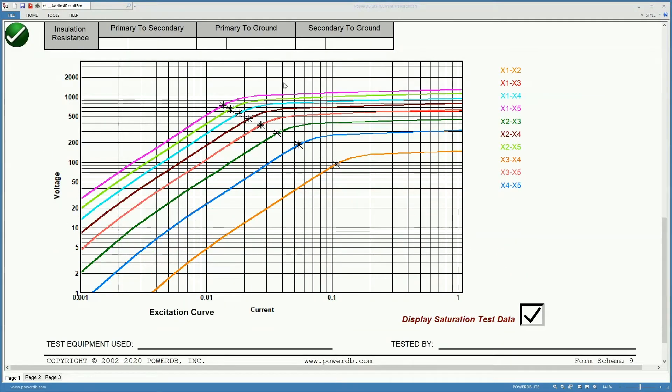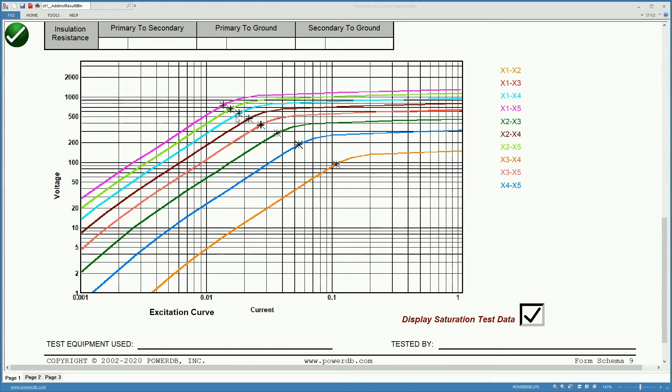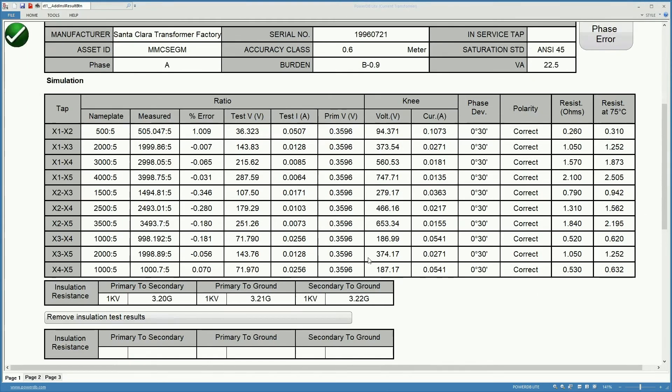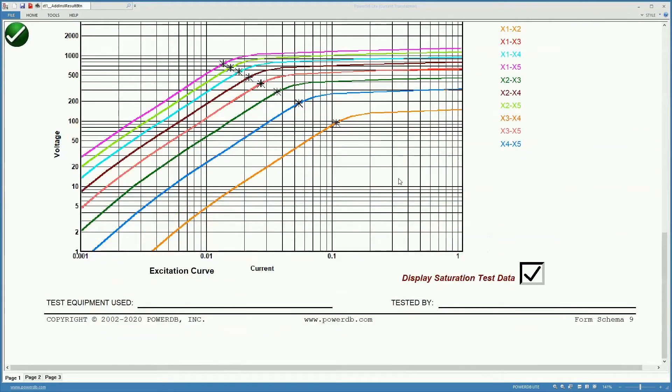If we scroll a little bit down, we get the excitation curves for the different taps. They are color coded. So for instance the X1, X5 is pink and it is the one on top over here. The values for the different knee points shown in this logarithmic graph coincide with the knee points calculated and shown on the previous graph. We can choose whether we want to display the saturation test data or not.